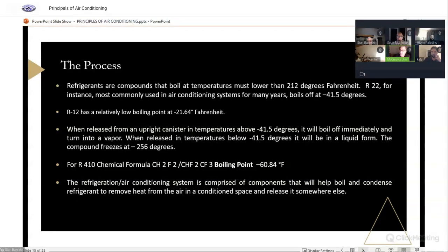So theoretically, that's correct. We also have different oils in the compressor, synthetic versus the old style oil. So they want all this to be uniform, compatible. Yes. However, back in the day, if your compressor failed, you were able to change that compressor. Today, you replace the whole condensing unit. Plus, the unit's probably old too. Well, if the compressor fails, unless it was struck by lightning or something like that, it is probably older. And what's the point of putting a brand new compressor in a case that's 20 years old?